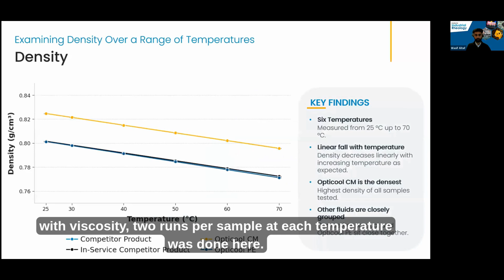Now, the key principle here is that the frequency at which that tube oscillates depends on its mass. And since the volume of the fluid inside is fixed and known, the instrument can then calculate the density directly from that oscillation frequency. It's quite a fast, precise measurement. And as the tube itself is thermostated, it's quite good for precise temperature control, again allowing us to get density over a range of different temperatures. And again, as with viscosity, 2 runs per sample at each temperature were done here.